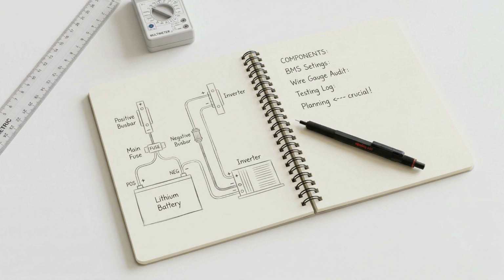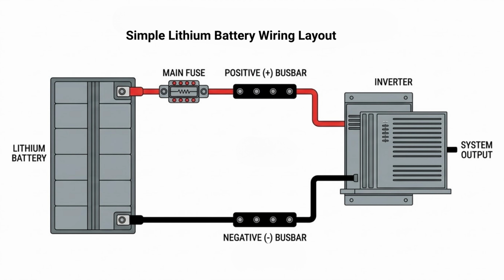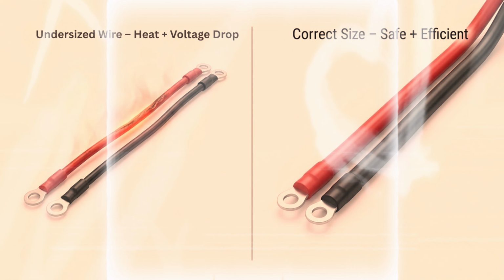Let's start with why lithium wiring needs extra care in the first place. Lithium batteries behave very differently from traditional lead-acid batteries. They can deliver and accept high current very quickly, which is one of the reasons people love them. But that same strength is also what makes wiring quality so important. A lithium battery bank can keep supplying a large amount of current until it is nearly empty. That means your cables, lugs, fuses, connectors, and protection devices all need to be able to handle sustained demand without becoming the weak point in the system.